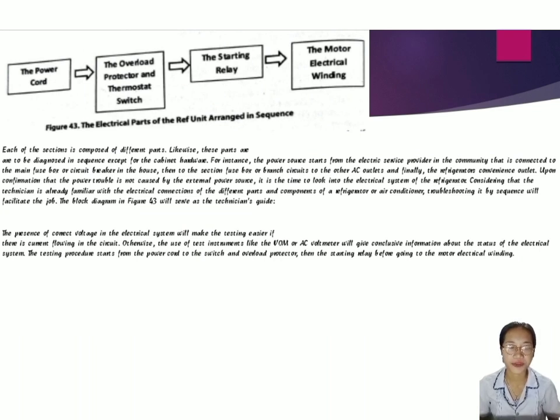The presence of correct voltage in the electrical system will make the testing easier if there is current flowing in the circuit. Otherwise, the use of a test instrument like a VOM or AC voltmeter will give conclusive information about the status of the electrical system. The testing procedure starts from the power cord to the switch and overload protector, then the starting relay before going to the motor electrical winding.